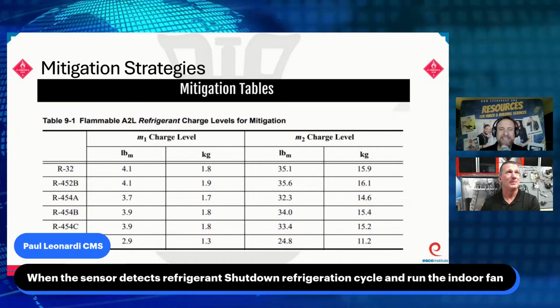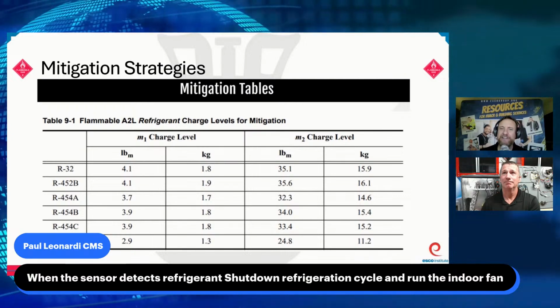And then whether it's a gas furnace or not, we have a heavy concentration of a potentially flammable substance. Man, if we could only dilute that down to where we didn't have as high a flammability, as much substance. I was always thinking about propane leaks. I said, make sure it's in an open area without an ignition source. So if we stop our ignition source, and then add some more air to that, let's run the blower. If we're moving the blower, we're moving air through that evaporator coil, and any of that refrigerant that's built up will then dissipate throughout the entire building, the structure, or the home. And so we've now brought that level below the lower flammability limit, and it's not possible to have a flame anymore at that point.